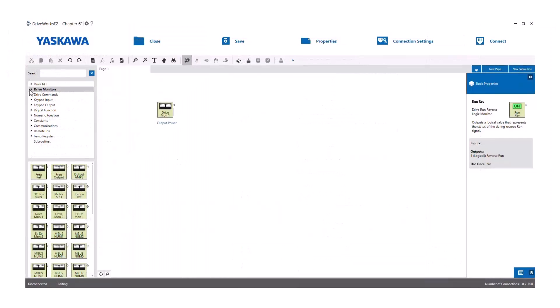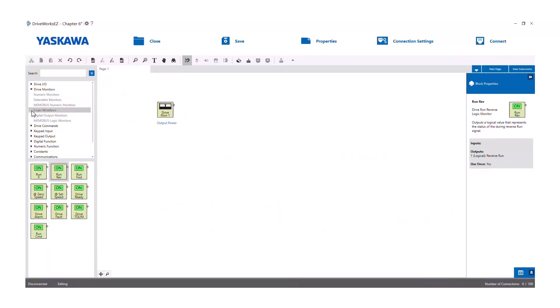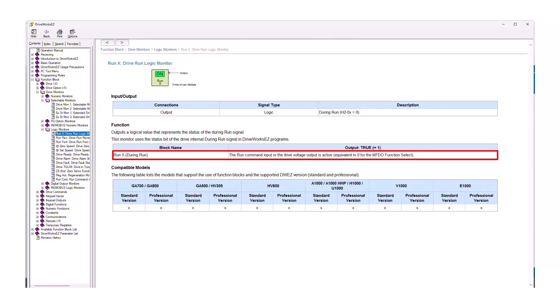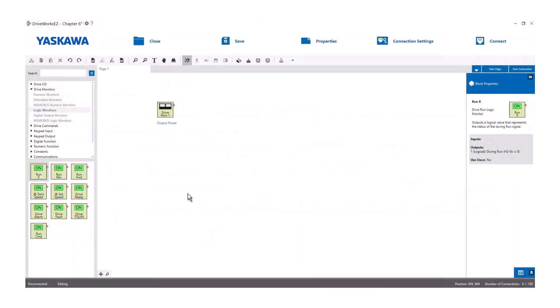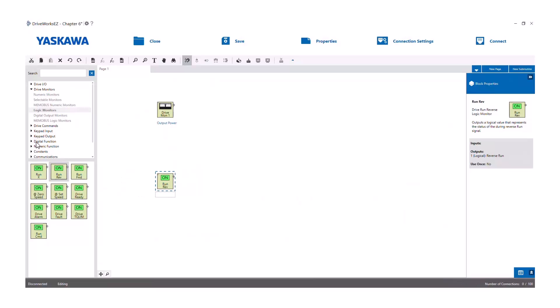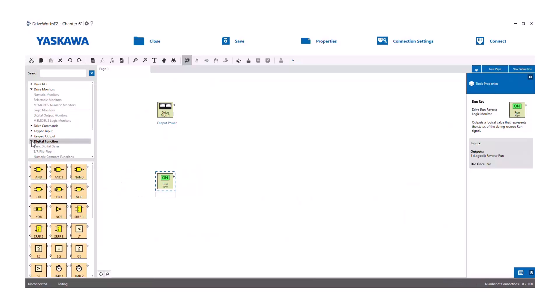There are also logical output monitor status blocks. These blocks with the green on icon will go true whenever the corresponding condition is true — on at zero speed, on a drive fault, during run, drive ready, and so on. Here's a little brain exercise: how would I reverse the logic of a run x input? If we right click and go to block help, we can see that an active run command input, or the drive outputting voltage, will cause this block to go true — normally whenever the drive is in a run condition. So if you want the output to go true whenever the drive is not running, just check the digital functions and use a not block. Make your connection and run it to whatever else is in your program, and it will invert the output.